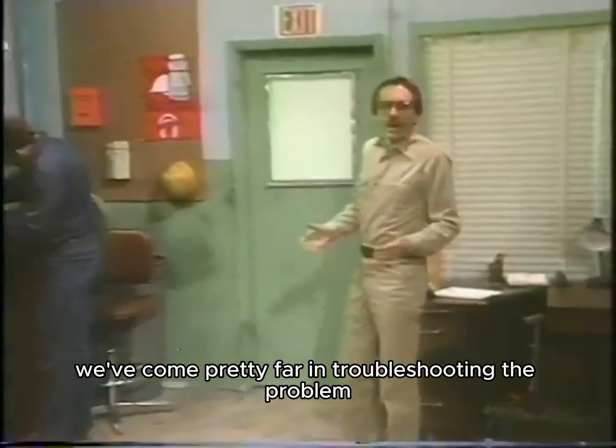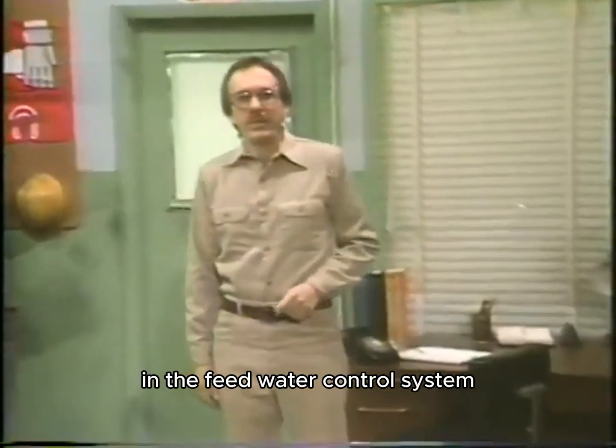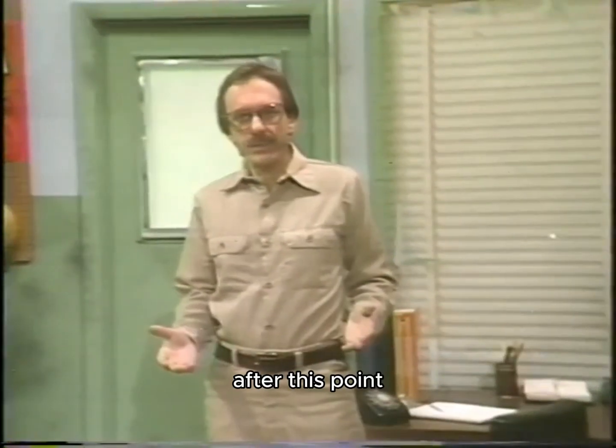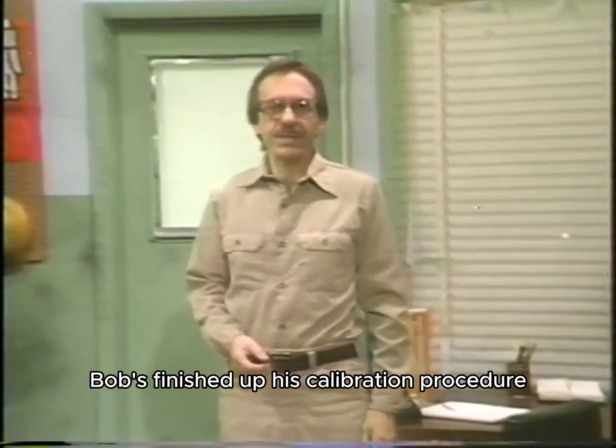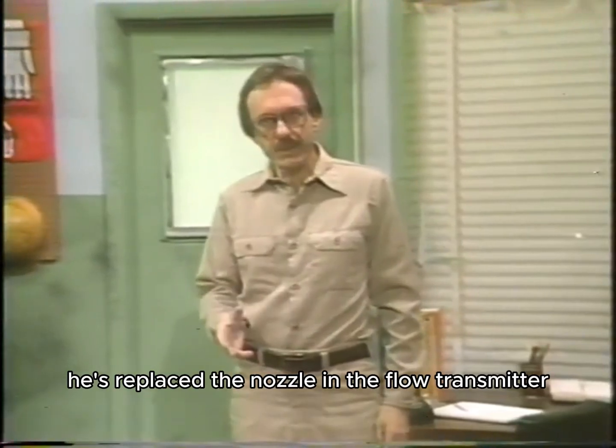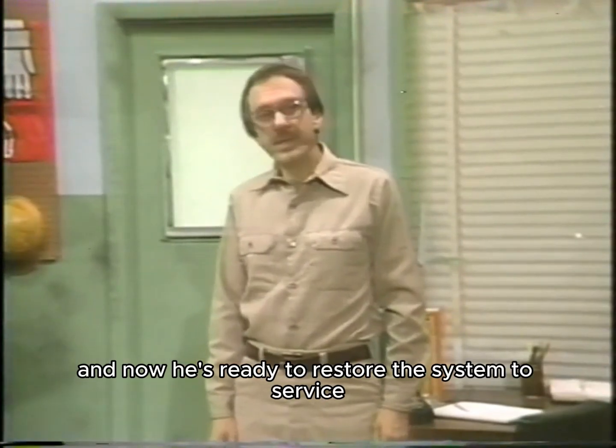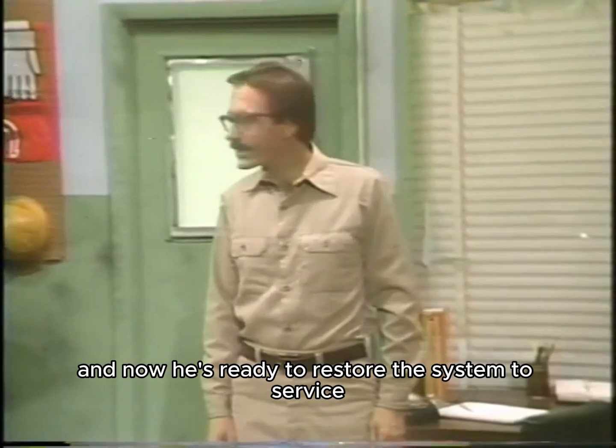Well, we've come pretty far in troubleshooting the problem in the feed water control system. Up to this point, Bob's finished up his calibration procedure. He's replaced the nozzle in the flow transmitter, and, well, now he's ready to restore the system to service.